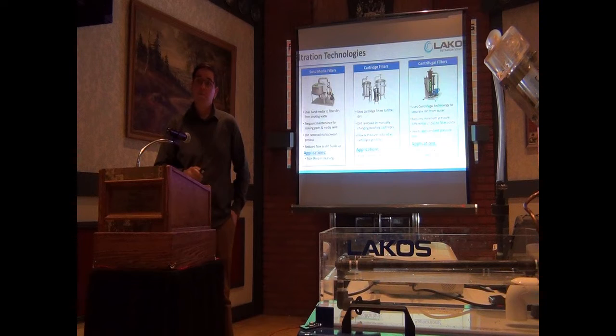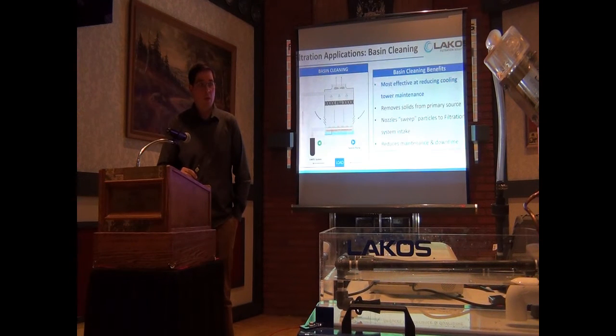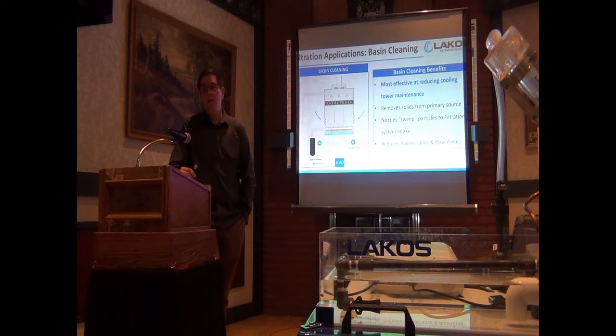So would you recommend putting your bleed off that on a cooling tower? I've been running into applications where I always recommend that type of filtration, that's where they put their bleed, so just less bleed off. But I'm starting to find a lot of applications where it's not. It's actually playing with the pressures in the system.